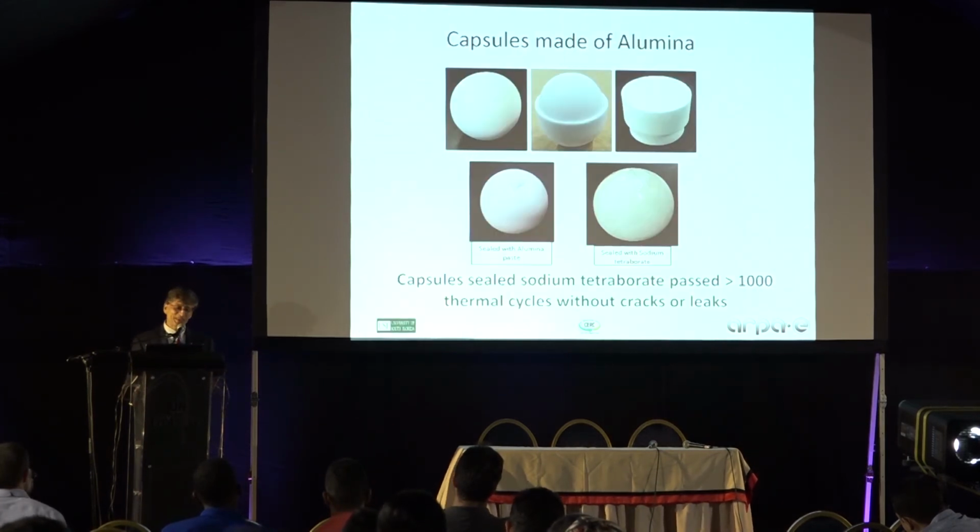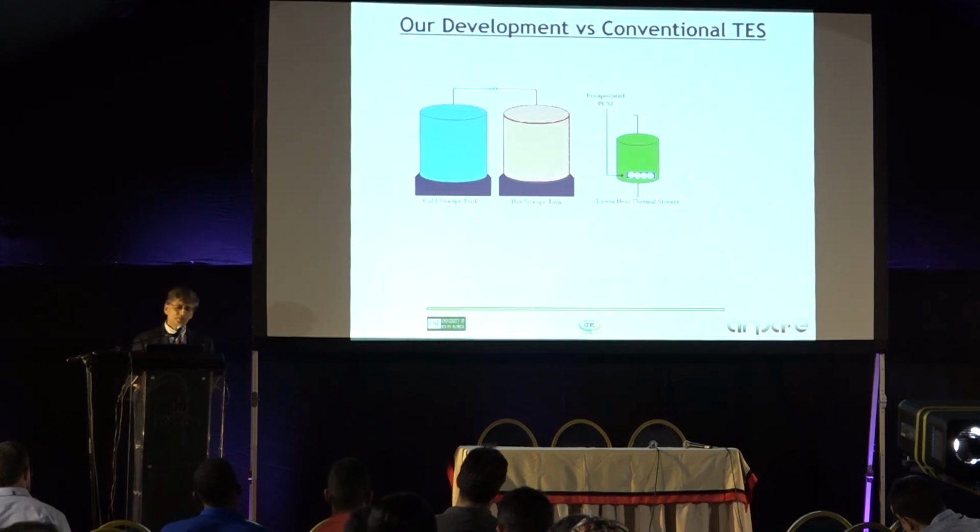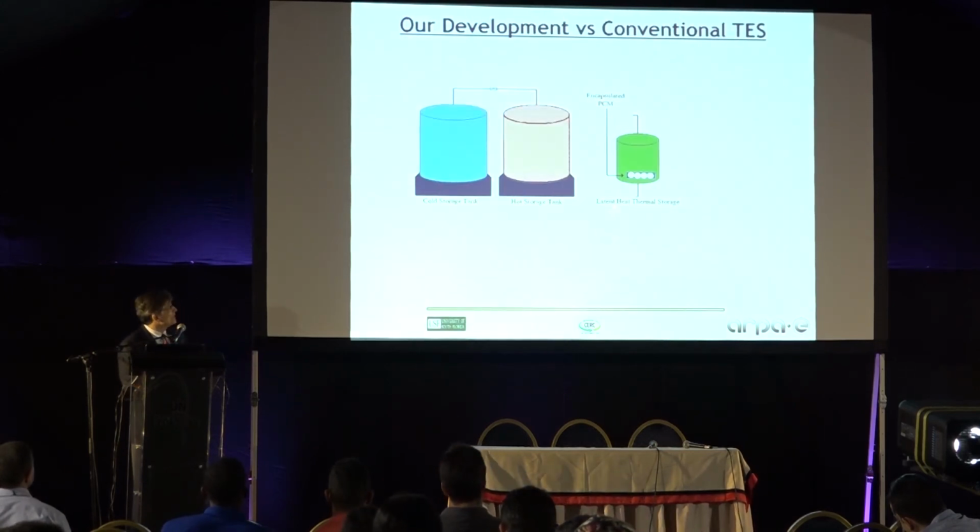But we were able to take care of that problem, and we were able to make these capsules, and we tested them to more than 1,000 thermal cycles, and there was no change in the properties of these capsules. None of them failed. So we know that these capsules will work as long as the solar thermal power plant will work. So with these developments, this is what the present thermal energy storage is.